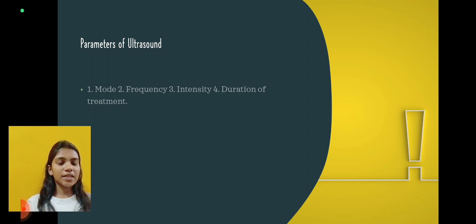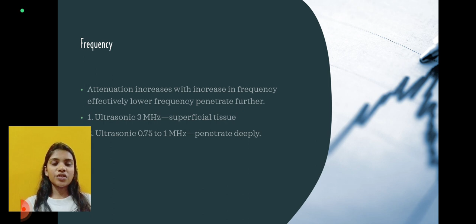Now, parameters of ultrasound. There are four parameters: mode, frequency, intensity, and the duration of treatment. Mode: continuous mode and pulse mode. Continuous mode produces more heat, and pulse mode produces less heat. So continuous mode is used for musculoskeletal conditions such as muscular spasm, joint stiffness, pain, etc. Pulse mode produces less heat, so it is used for soft tissue repair, for example, tendinitis.